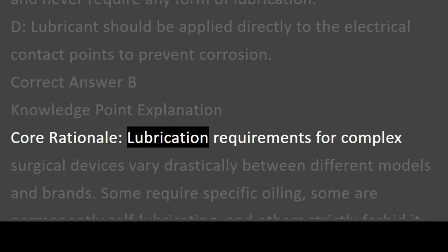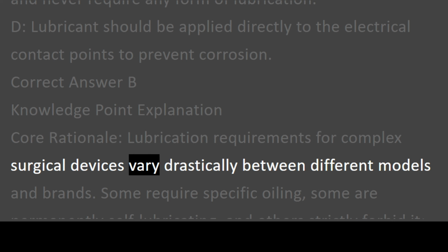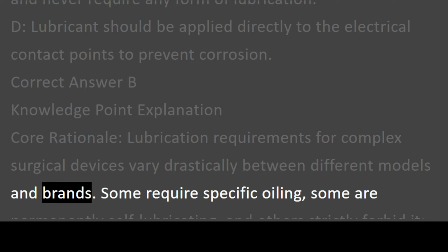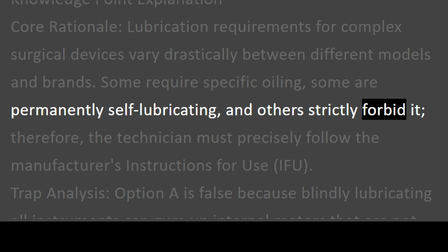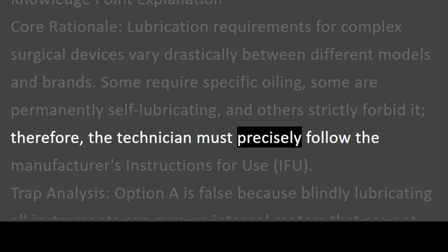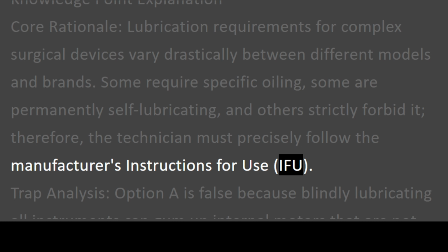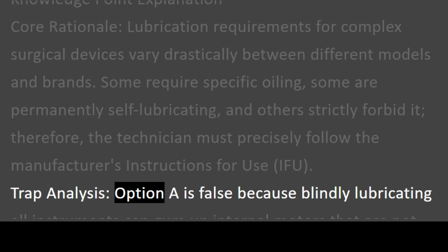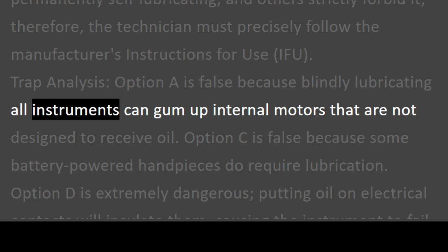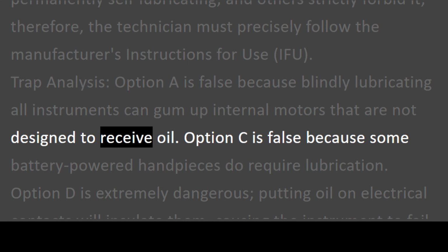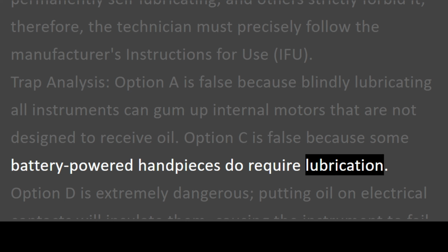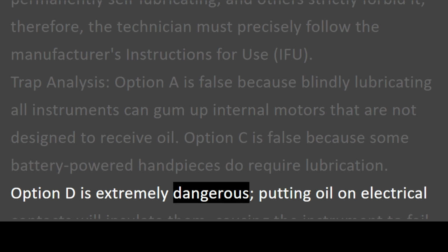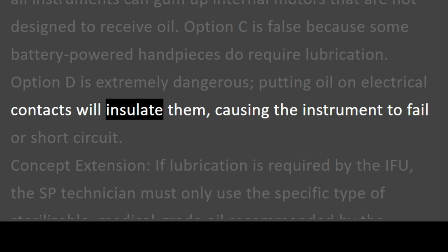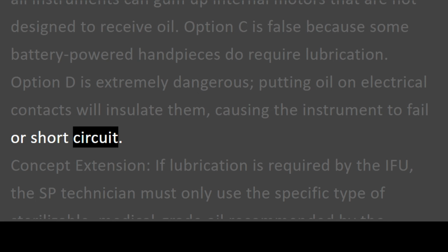Core rationale: lubrication requirements for complex surgical devices vary drastically between different models and brands. Some require specific oiling, some are permanently self-lubricating, and others strictly forbid it. Therefore, the technician must precisely follow the manufacturer's instructions for use, IFU. Trap analysis: option A is false because blindly lubricating all instruments can gum up internal motors that are not designed to receive oil. Option C is false because some battery-powered handpieces do require lubrication. Option D is extremely dangerous. Putting oil on electrical contacts will insulate them, causing the instrument to fail or short-circuit.